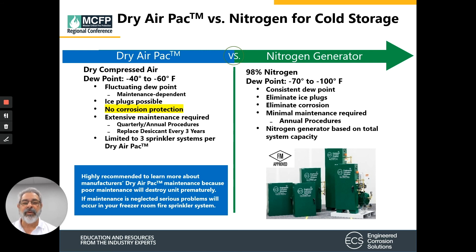In a comparison between Dry Air Pacs and nitrogen generators: Dry Air Pacs have a fluctuating dew point with a lowest point between minus 40 and minus 60 degrees Fahrenheit, are maintenance-dependent, have the potential for ice plugs, provide no corrosion protection, require extensive quarterly and annual maintenance procedures, require desiccant replacement every three years, and are limited to three sprinkler systems per unit. Nitrogen generators produce 98% pure nitrogen with a dew point as low as minus 100 degrees Fahrenheit. The dew point is consistent, ice plugs are eliminated, corrosion is eliminated, maintenance is minimal and only annual, and the generator is sized based on total system capacity.